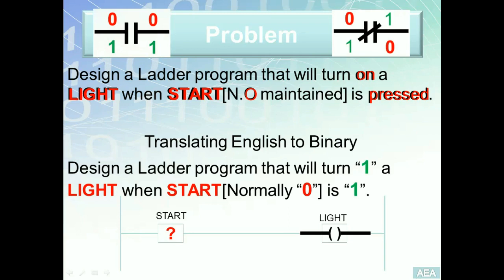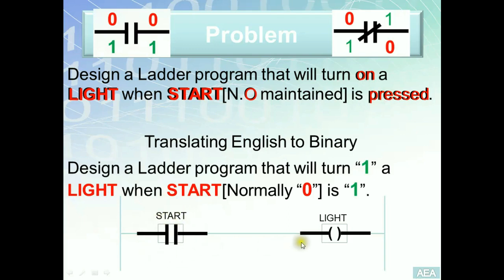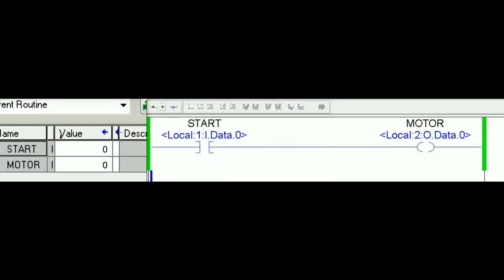This is a buffer relationship, which is why we can 100% determine that choosing XIC to represent Start will fulfill the requirement. As long as Start is in the open state, the XIC instruction will be false and the light will be off. Anytime the switch is pressed to close, the XIC instruction will be true, it will energize the OTE, and the light will turn on.